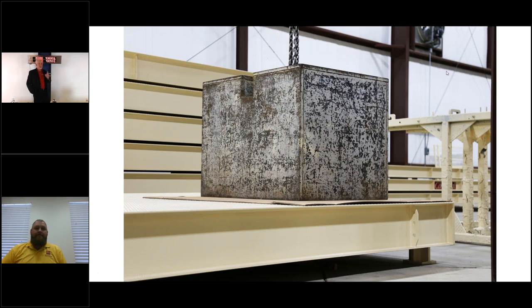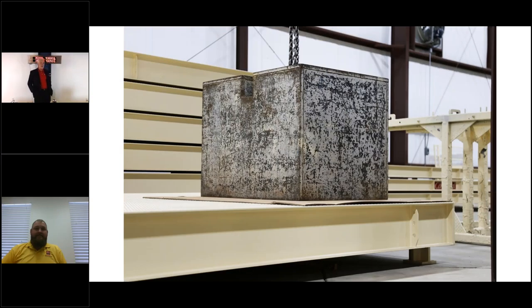That's a great advertisement. You guys saw a few minutes ago, I was actually leaning over the 225 indicator upside down and got into calibration. That was just how easy it was to get in smart cal on the 225. So that's really a great testimony. And you see there on screen now, we just showed putting test weights on the scales before we ship them.